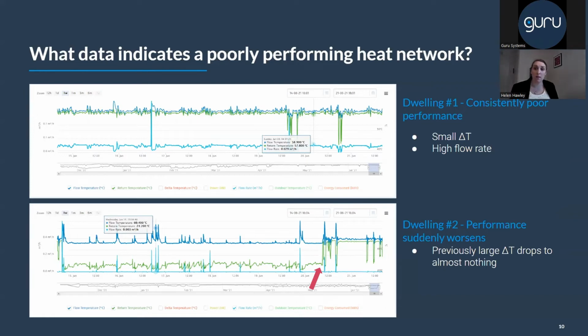The second graph shows a system that was running successfully. You have a nice big gap between the dark blue and the green, and then towards the end of the graph on the right hand side, you can see that all of a sudden the flow and return temperature collapse together and start tracking each other. And this is where something has gone wrong with the system. Because this heat network was being monitored, when there was a fault, they could see that there was a fault and go and investigate the situation appropriately.